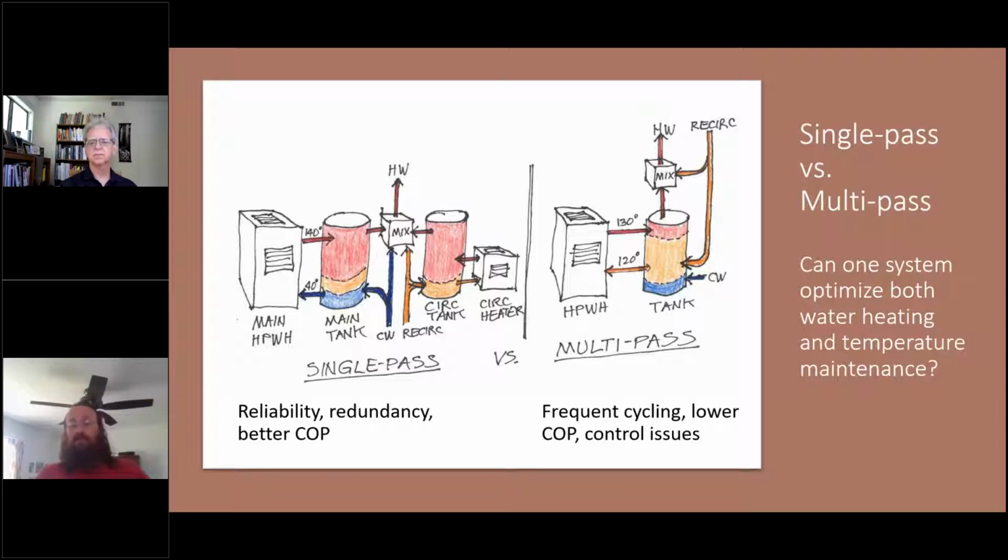Those LBPP projects that pursue that often are forced into heat pumps for that recirc heater, meaning electric resistance doesn't pencil, right? It's too much energy loss. And while those recirc heaters are usually small in capacity, when they're heat pumps, they run for the entire year, really the entire life of the building. And so that energy delta is just massive when you figure it up. So one thing to keep in mind, heat pumps can be used as recirc heaters.